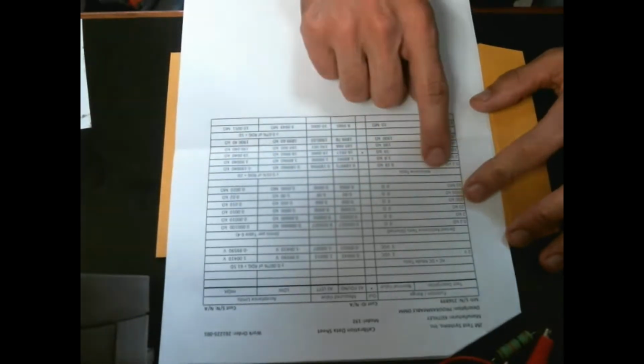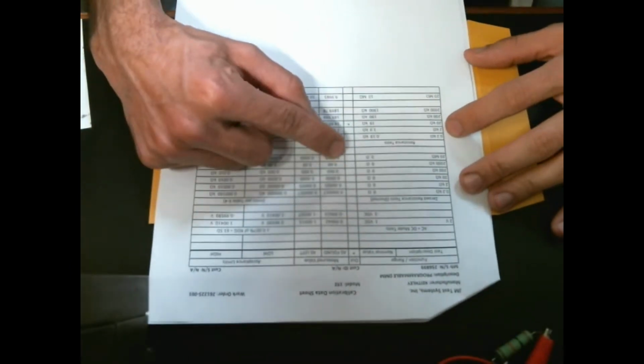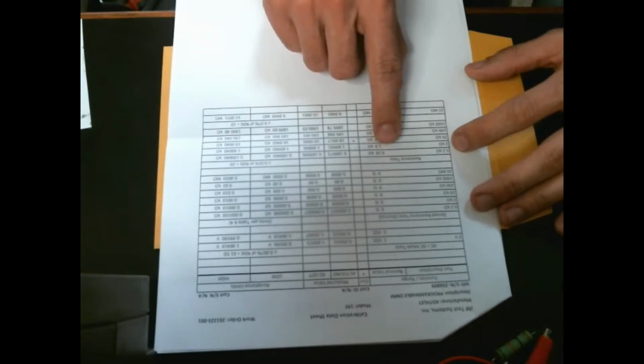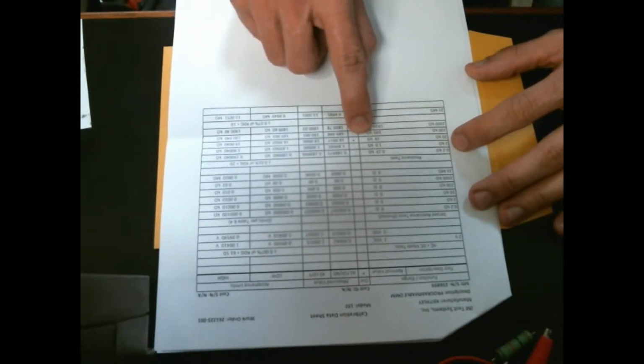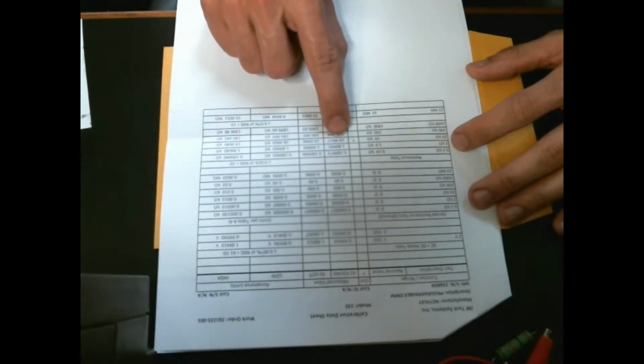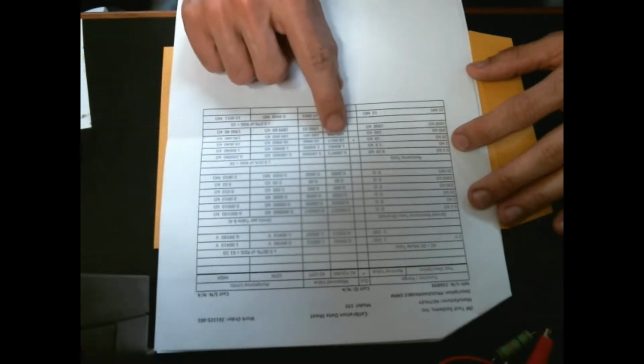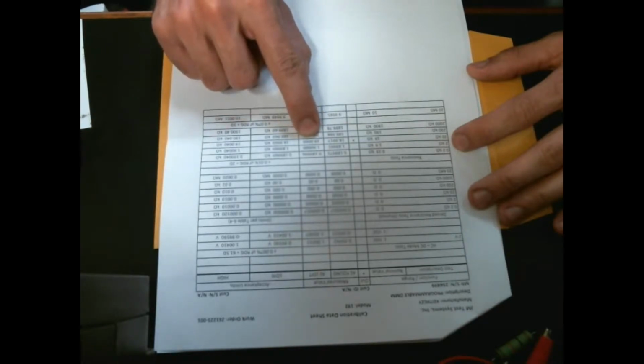The resistance ranges, I had assumed would be fine, and for the most part I was right, except for, once again, this 20,000 ohms range, which is the same range, incidentally, that was out on the DC that I knew of. So that's not totally unexpected, but it is actually kind of strange also that when it was shorted, it didn't show anything. But whenever they did actually put the resistance standard on it, it showed that it was out. And not by very much. Just a, what would that be? 0.01-ish ohms. But they got it dead on right now.